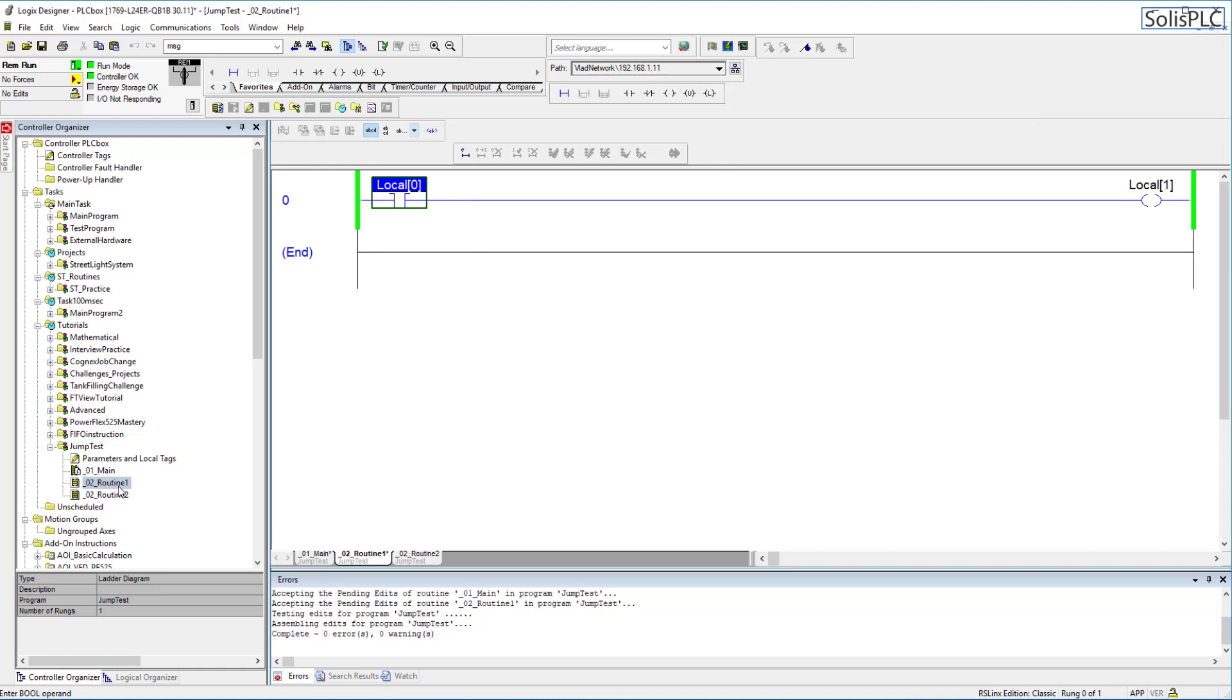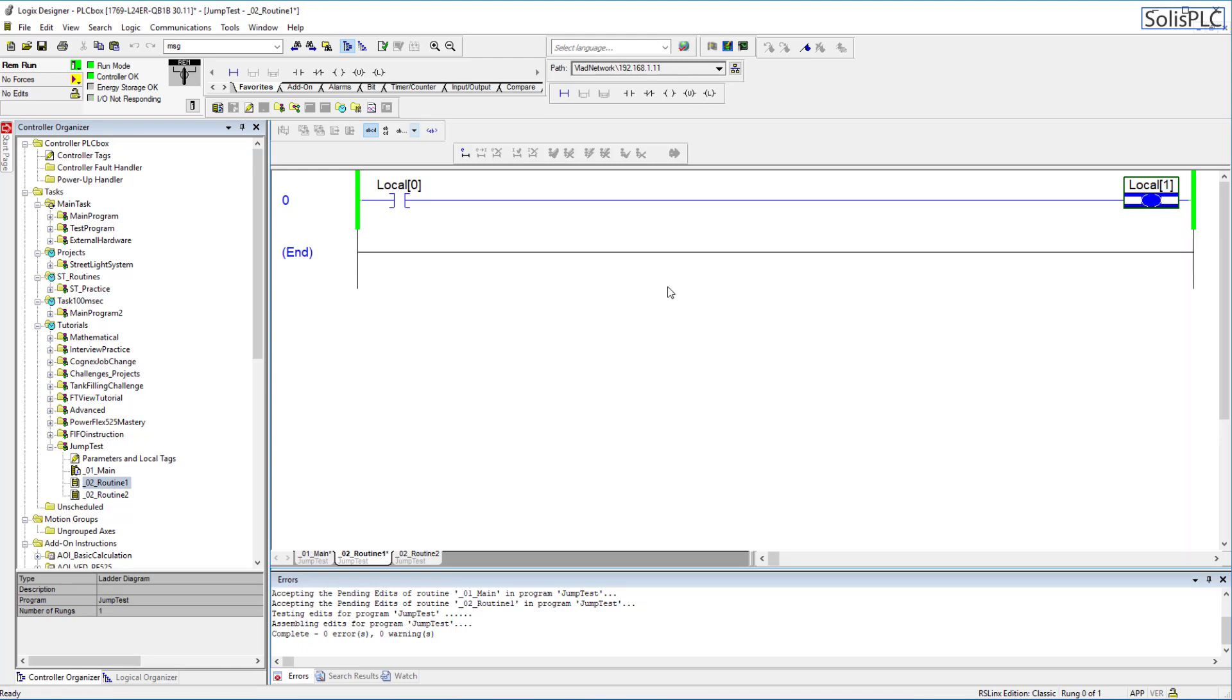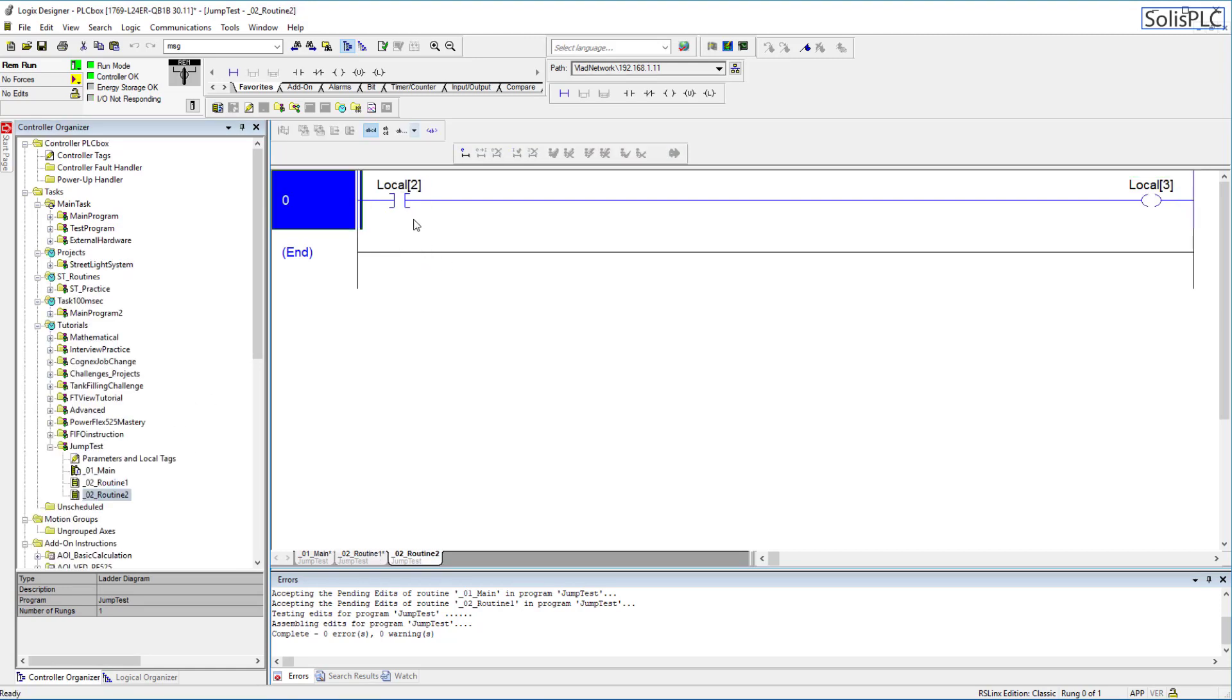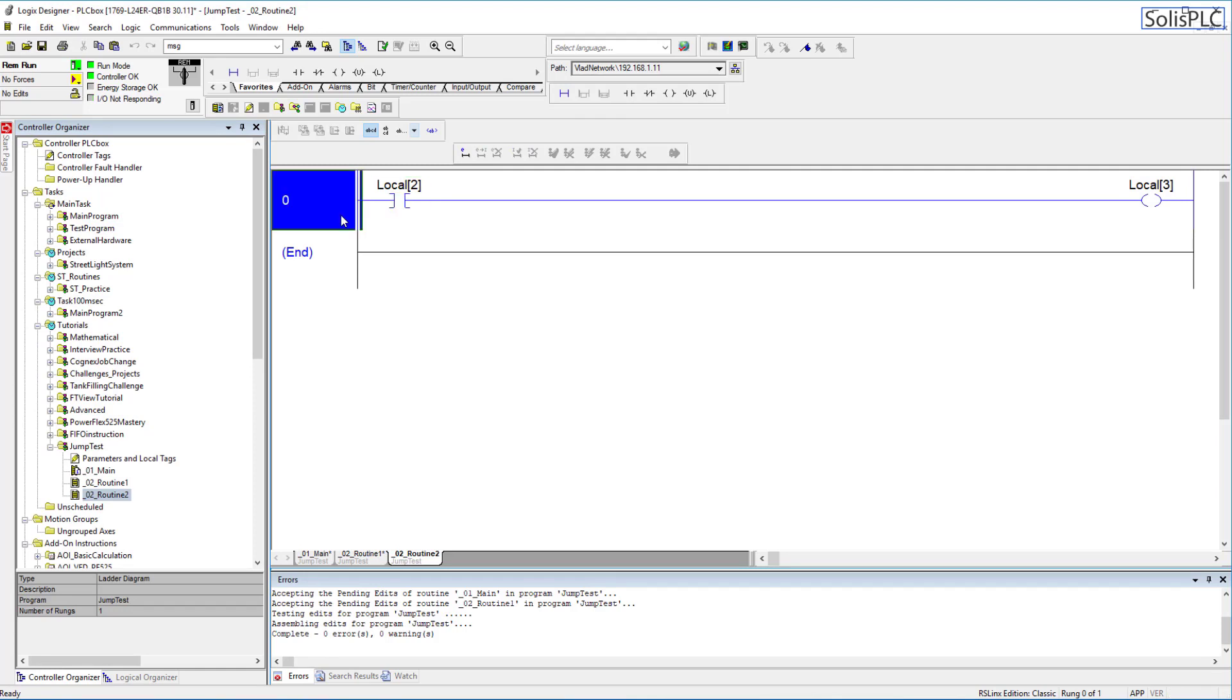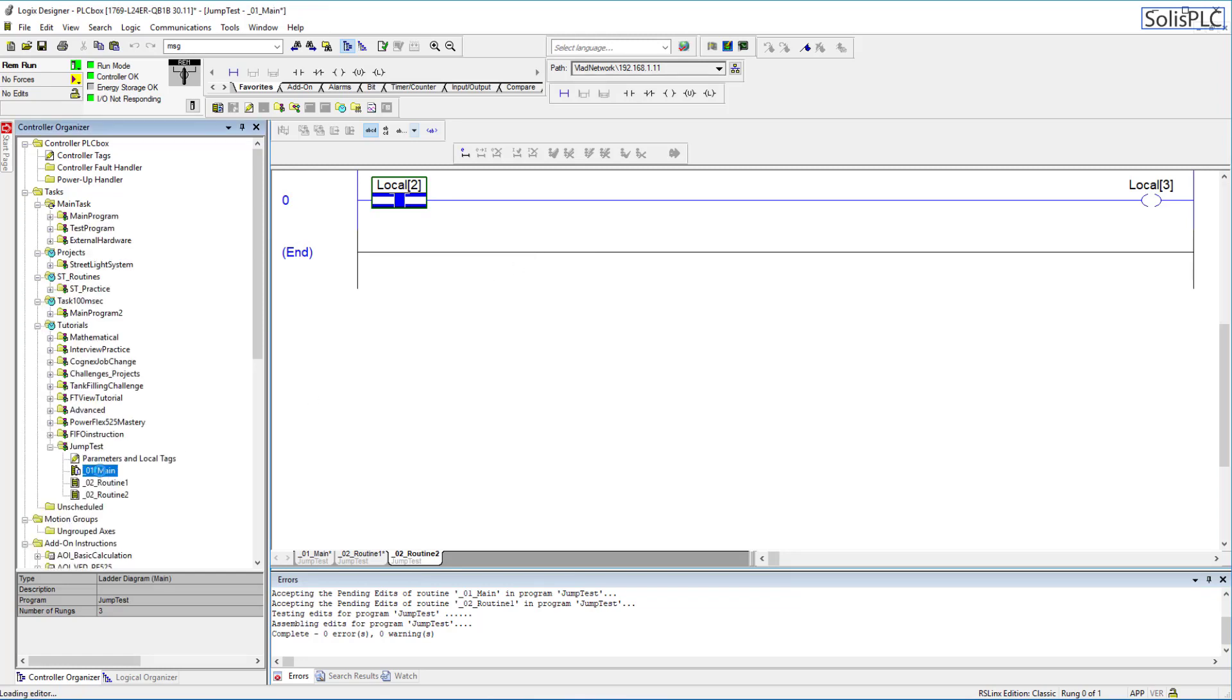If I flip over to routine 1 by double clicking on the routine name you will notice that on the left hand side my bar here as well as on the right hand side is going to be green. Now this green indicates that this routine is being executed somewhere from the code. Do notice also that I am live with the PLC therefore the routine is being called and is being executed live. If I go to routine 2 since I've shown you that I had no calls to routine 2 at all you'll notice that this routine has no green color on either side which means that this ladder logic is not being executed at any point in time by the program. So that's the way to find out whether or not something is being executed.